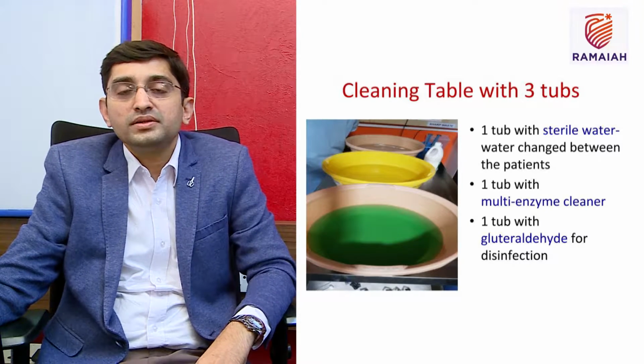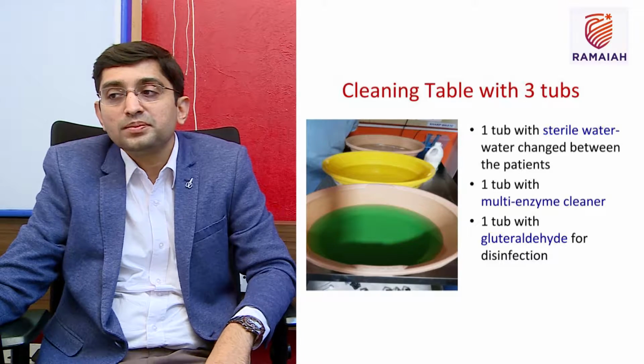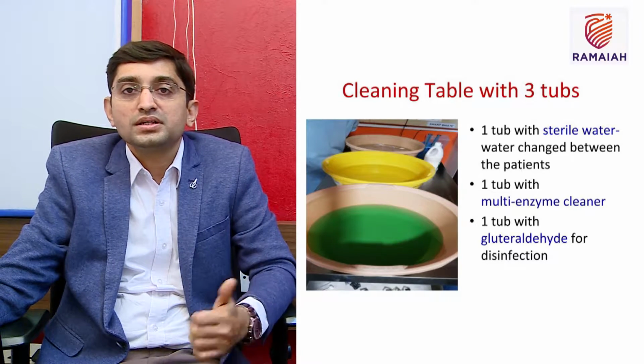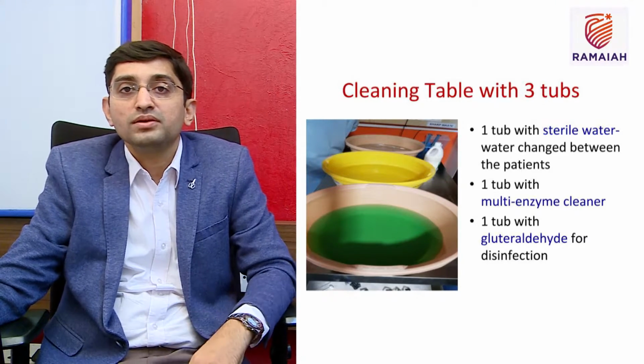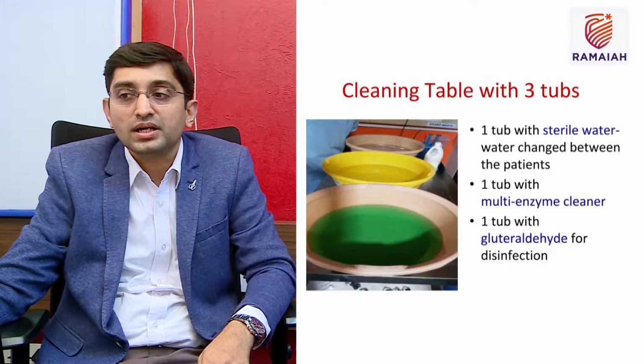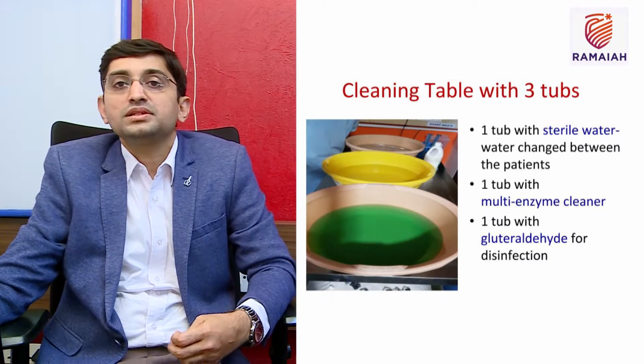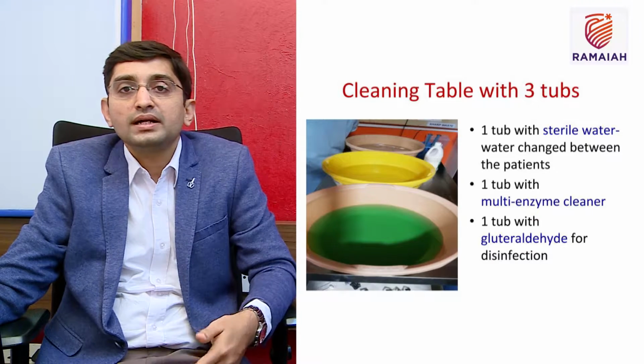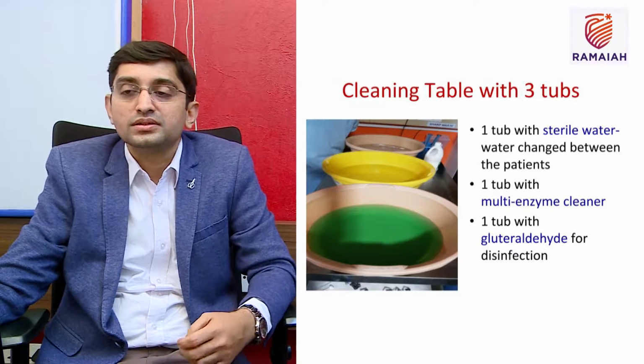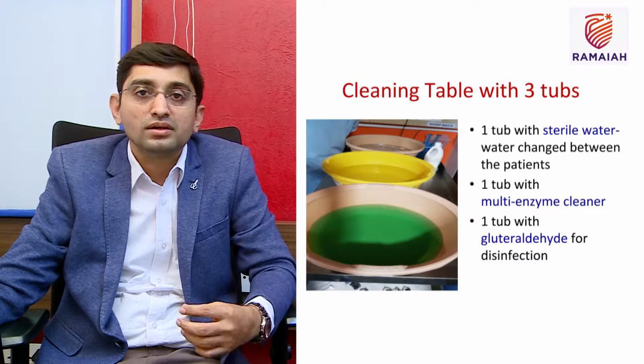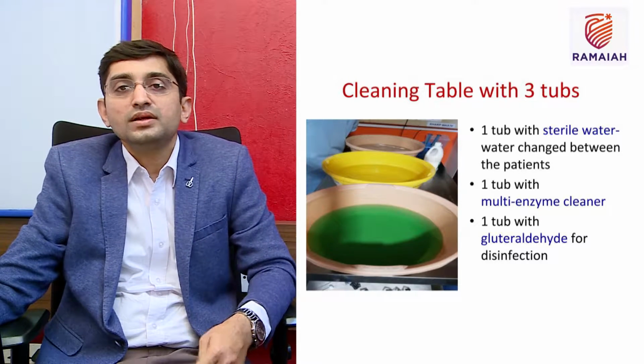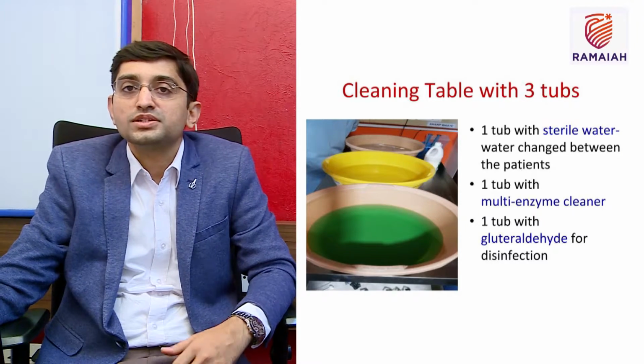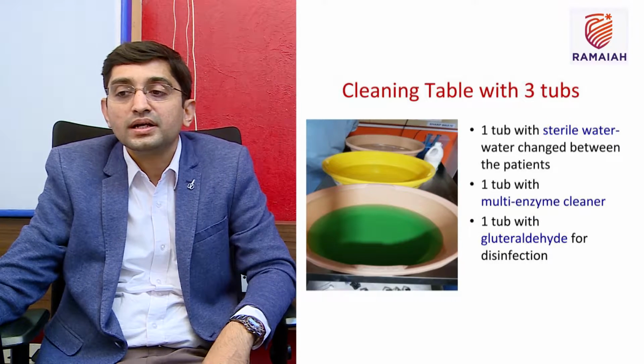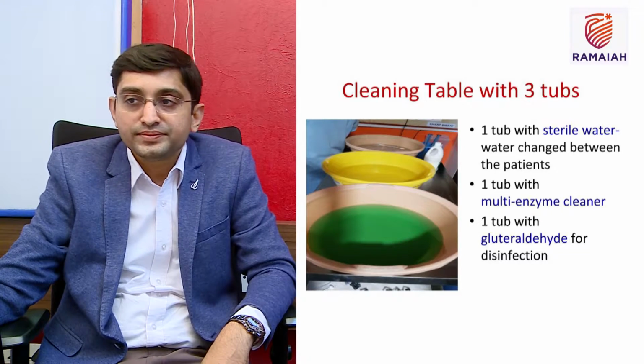The first tub will be with the sterile water, which is changed between the patients because we don't want the patient secretions or the debris contaminating between the patients. So we should always change the sterile water. The second tub is with a multi-enzyme cleaner, because that will act like a sterilization sort of cleaning as well as brushing all the ports. And then the last one will be a disinfectant solution, which is predominantly a 2% glutaraldehyde, that is for disinfection.